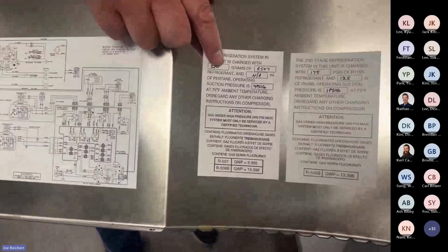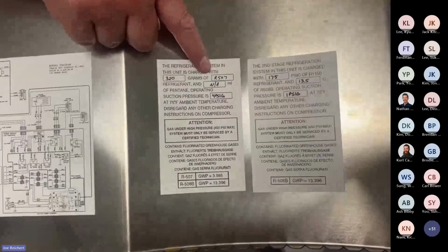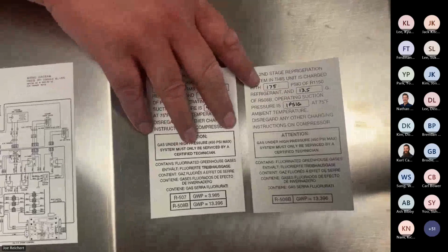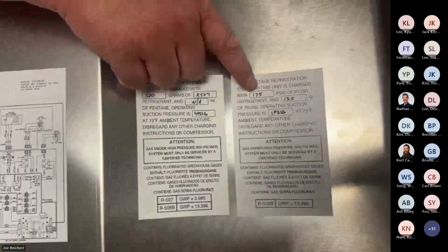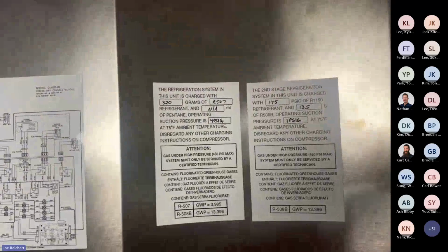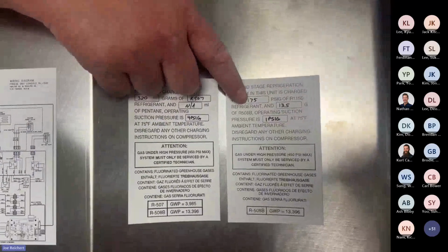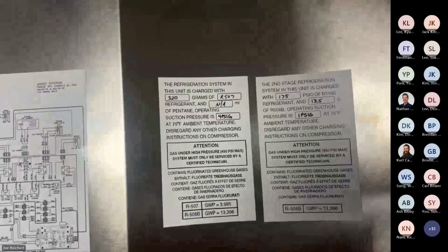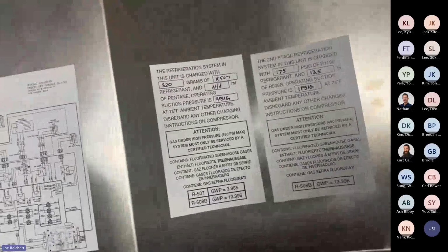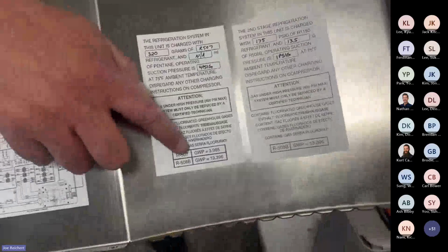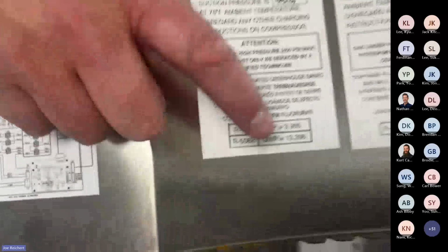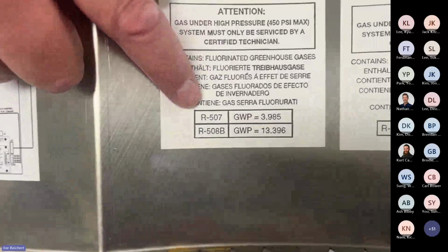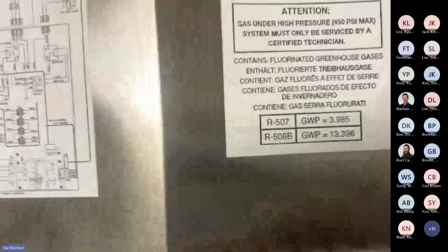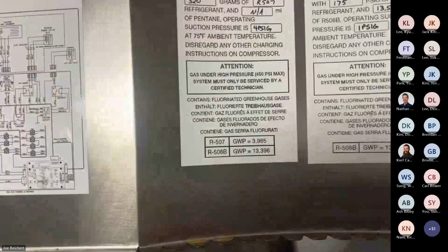This is a bit of an older system, so it still has 507 in the first stage, and then R1150 in the second stage for the -105s. It tells you what pressure it was charged to, the suction, and tells you the same thing on the first stage as well. It also gives you your GWP numbers. I've had some customers request those, but those are listed right on the stickers as well. Your global warming potential numbers. Now there are changes coming up on gas as well, so probably more changes of gases.